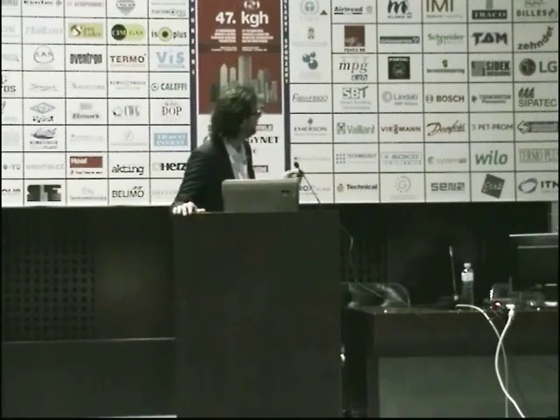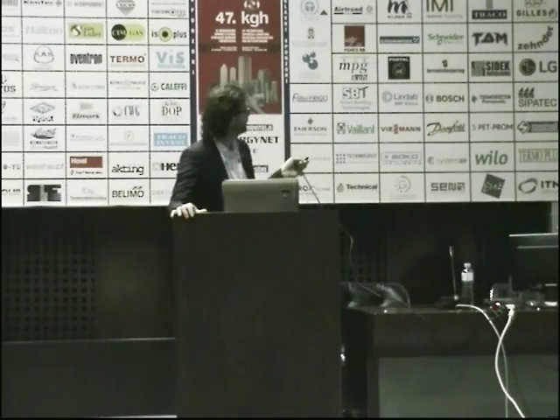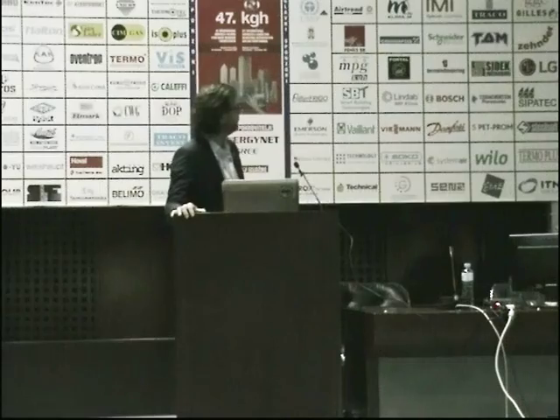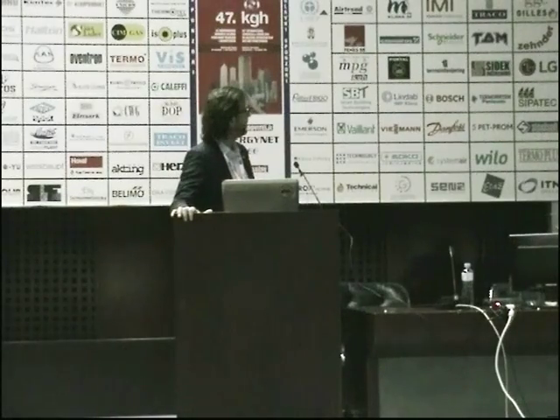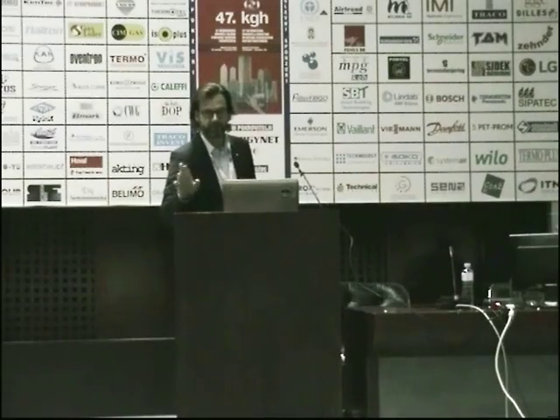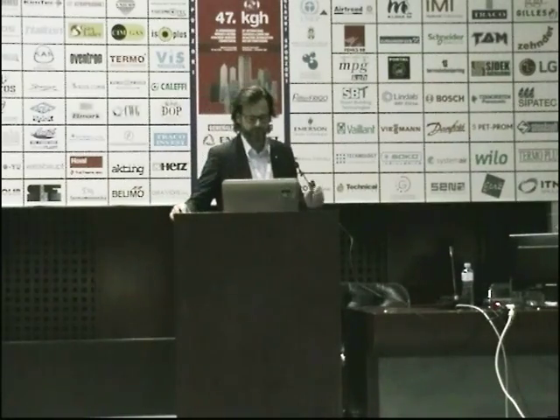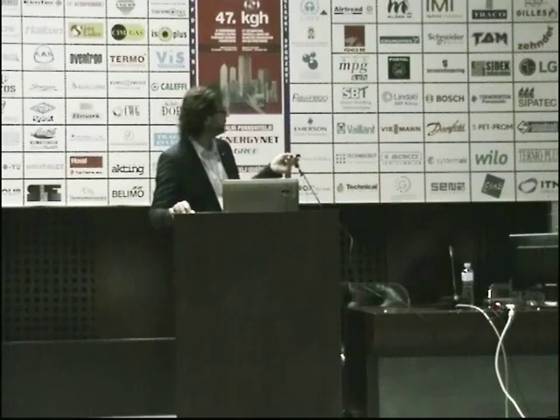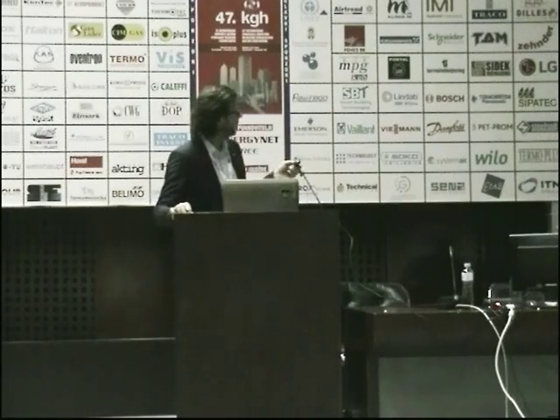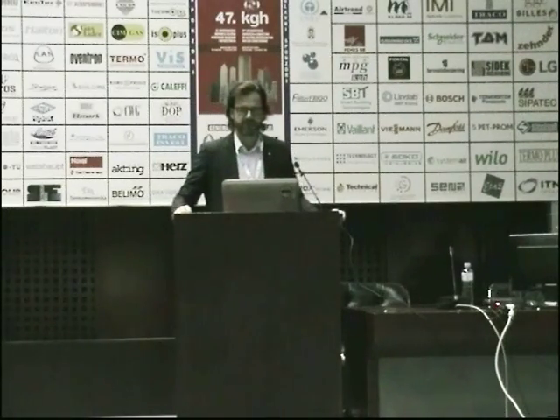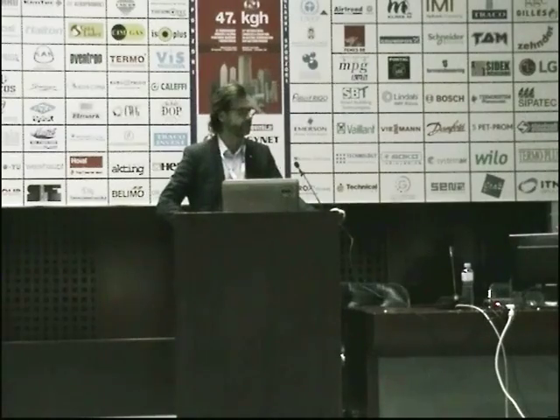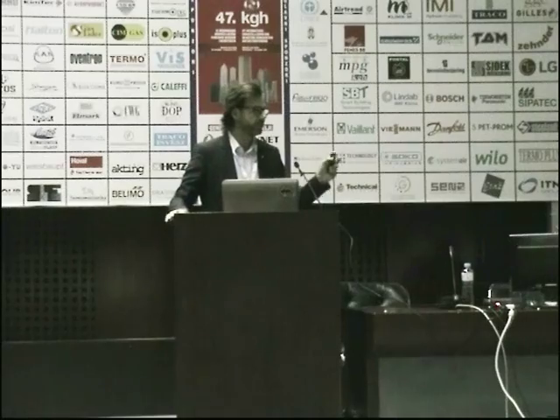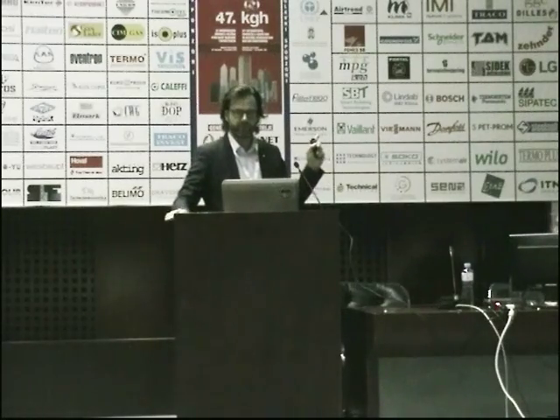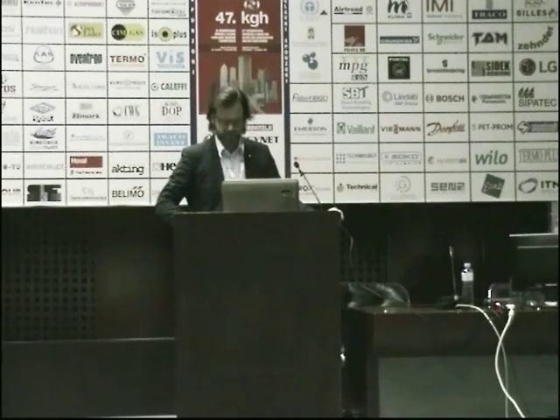You also can see the filling amount of the systems. We have 350 kilowatts of ammonia capacity, and the charge is 40 kilograms, 0.11 kilogram per kilowatt. So very, very low charges. The machine is in a machine room, so if there is an accident, there is no harm to any customer. The oldest system is now running since 1994 in the same application.